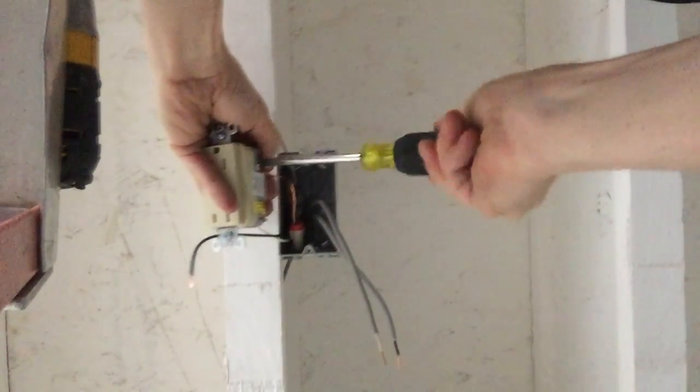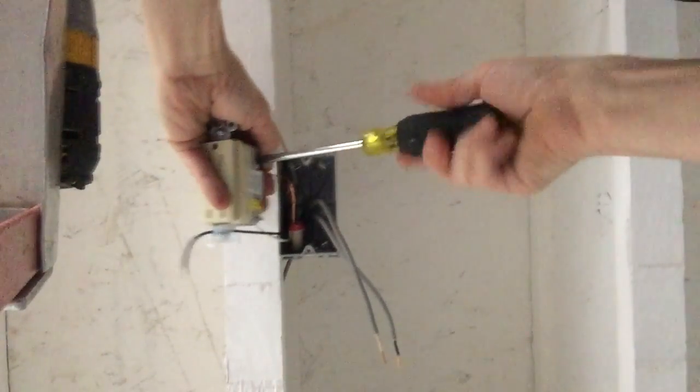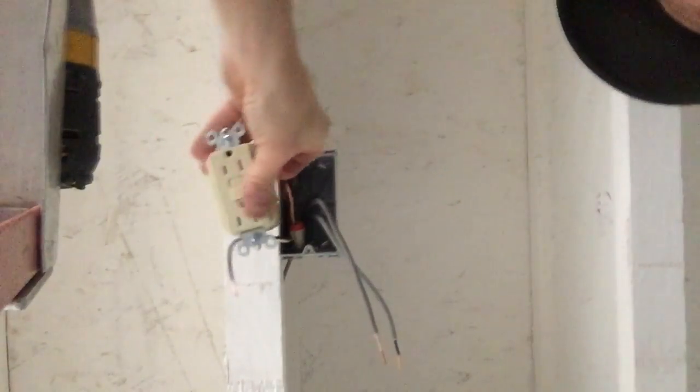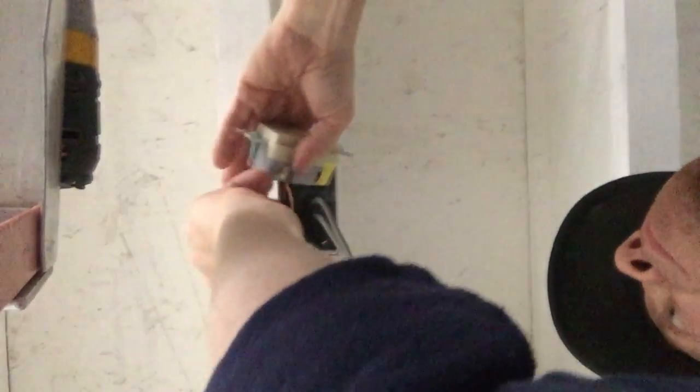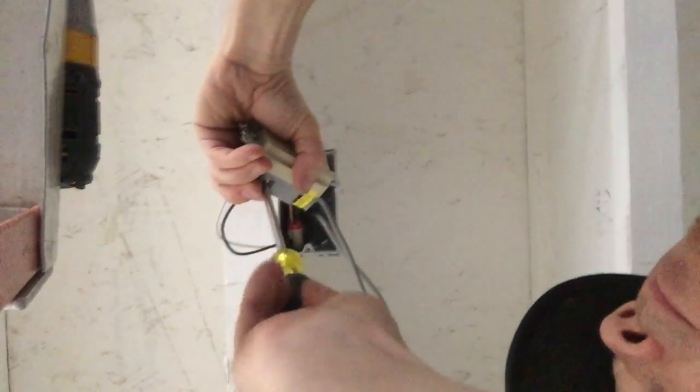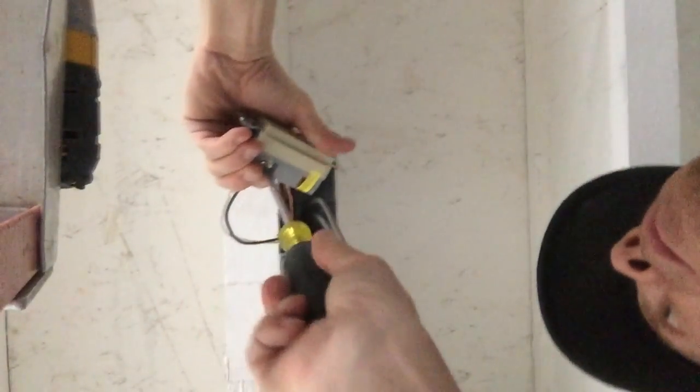One of them is your line voltage which is the one that is actually bringing the power, and then the other one is considered the load. That's the one that might go feed another outlet but will not work unless the line is connected. So you're going to connect the line separately from the load.